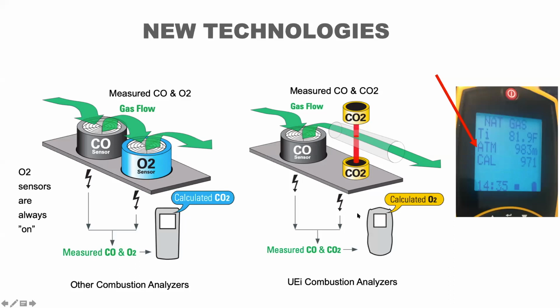And then the CO2 level with its flue gas, the fuel code, creates the calculated O2, calculated oxygen. An interesting thing here, as I point out on the display of the screen in the 161 as it's starting up, it has ATM. That's not the place where you get the cash from. This is the atmospheric pressure of 983 millibars.